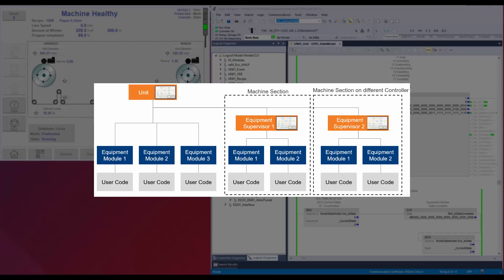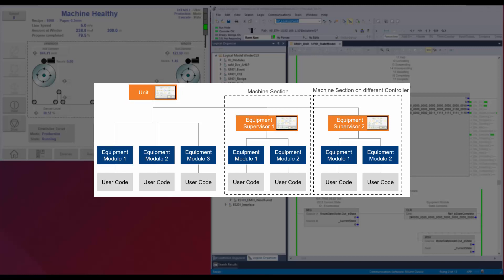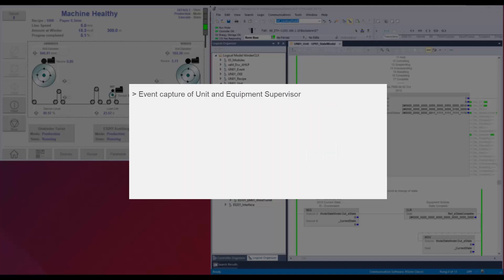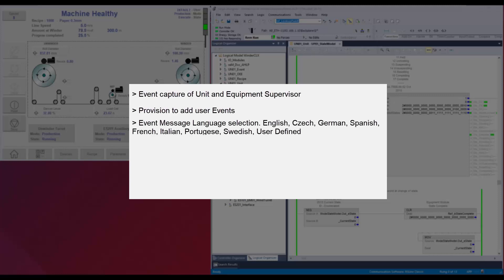The framework has three types of modules: unit, equipment supervisor, and equipment module. The physical model of unit and equipment are derived from the ISA-88 standard. The procedure model of modes and states are derived from TR-88 2015 version. The framework has event capturing of states and modes, and also provision to add custom events to help in easy diagnostics. The event language can also be selected from available languages, and it is also possible to add a custom language compatible with ASCII characters.